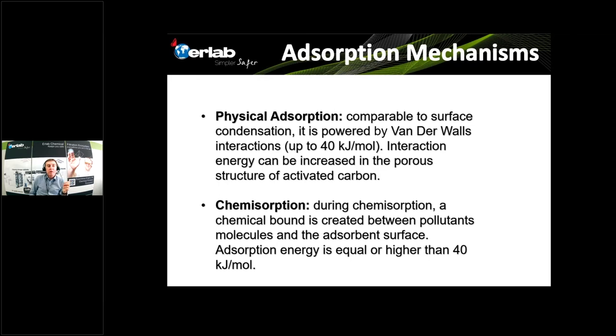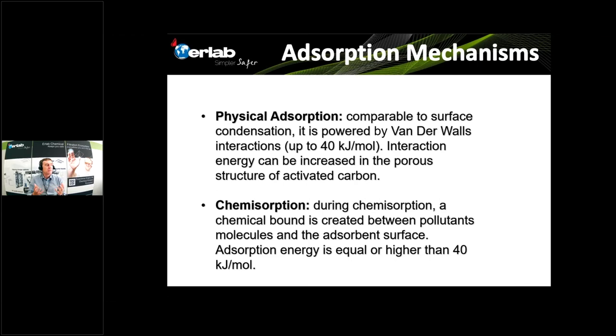Physical adsorption is very useful to trap non-polar solvents, but less efficient for polar molecules. That is why we also define a second type of adsorption called chemisorption. During chemisorption, we create chemical bonds between the pollution and the surface of the activated charcoal, and in that case there is no risk of desorption at all. When you want to trap a mix of VOCs, it is very important to achieve both types of adsorption: physical and chemical.